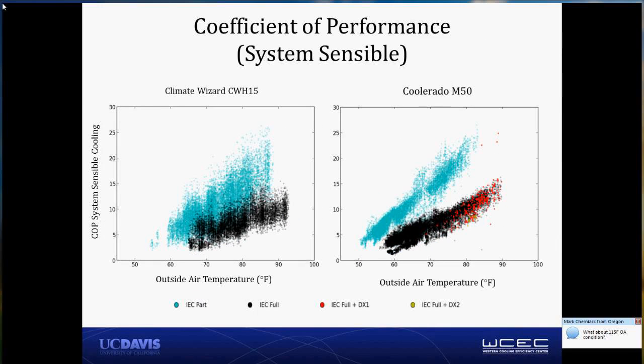Those red dots are showing when the combined system is operating in indirect evaporative plus vapor compression. There's even some yellow dots, where we're running indirect evaporative plus DX2, second stage compressor. And what we're marking here with those red dots is the coefficient of performance for the indirect evaporative cooler. We're not marking out the combined coefficient of performance for the overall system, which we could also do with all the performance data we had, but we've constrained our evaluation to the indirect evaporative equipment alone.